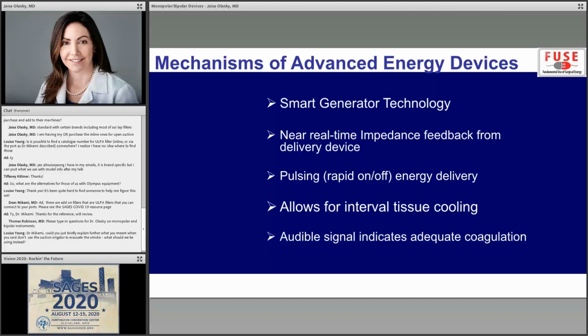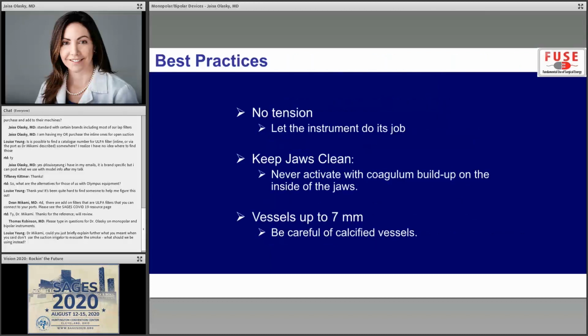counteractive. So best practices, also tension is really important with bipolar. If you're using it to dissect, you may be pushing on tissue, and that's fine, but remember, when you go to use it for energy, if you're holding the vessel, you don't want to be holding it up or putting any tension on it, because then it won't get the adequate seal.